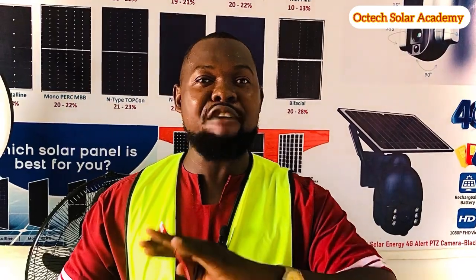For those of you who also want to do general repairs or designs on MPPT solar charge controllers, remember some MPPT solar charge controllers, like hybrid inverters or hybrid MPPT solar charge controllers, require a very high voltage to be powered on. So you don't need a series of panels. Some hybrid inverters need a minimum voltage of up to 50, 60, or 70 volts before the MPPT or hybrid inverter will power on. This device can generate as high as 60 DC volts to your solar charge controller while you're working on it.